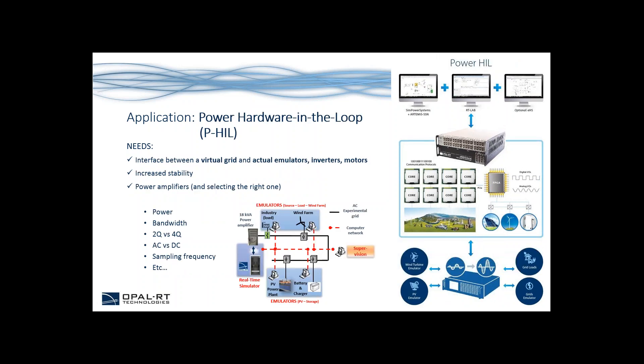The third application is power hardware-in-the-loop. When related to microgrids, we're talking about an interface between a virtual grid and actual emulators, inverters, and motors. We need to ensure increased stability due to power amplifiers being in the loop. One challenge is selecting the right power amplifier based on your needs — considering power, bandwidth, two-quadrant versus four-quadrant, AC versus DC, and sampling frequency. At Opal RT, we work with various third-party amplifier manufacturers to help you select the right one. The real-time simulator simulating the virtual grid is interfaced with a power amplifier, which then connects to wind turbine emulators, PV emulators, grid loads, motors, and inverters.